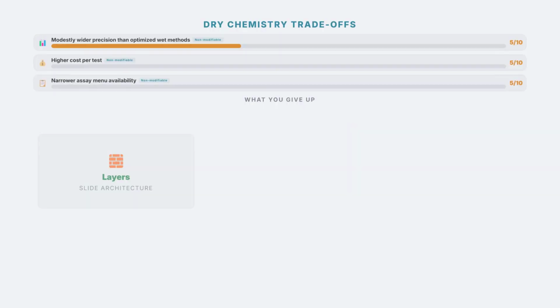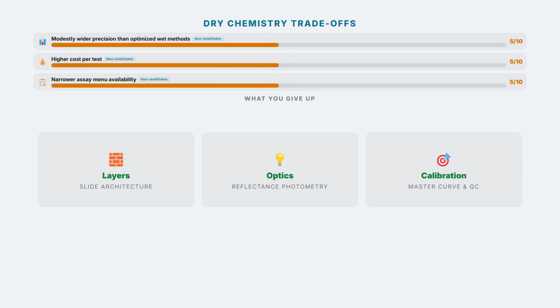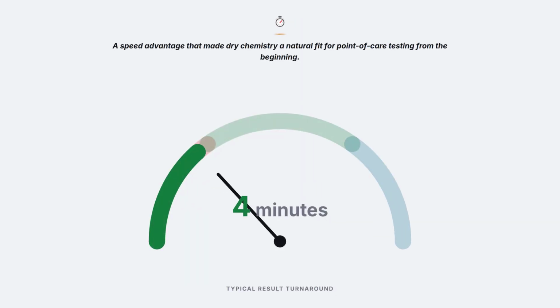None of this is a free lunch, and being upfront about the trade-offs matters as much as the advantages. Precision can run modestly wider than an optimized wet method. The slides themselves cost more per test. And a genuinely diverse assay menu on one wet chemistry platform can outstrip what's commercially available as dry slides for less common analytes. Turnaround time is where the technology's design philosophy shows most clearly.